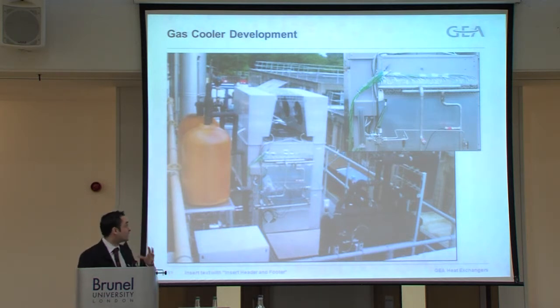This is to ensure we had a complete understanding of the pressure drop characteristics of the working fluid through the gas cooler. We also installed an IR camera so we could visualize the temperature distribution across the gas cooler. And we had accelerometers, which, as you can understand, they have a working fluid potentially going from 120 to 34 degrees C. There's a lot of different expansion and contraction going on within that coil block. And to ensure the coil block wasn't damaged in any way, we measured with accelerometers the movement of the coil.